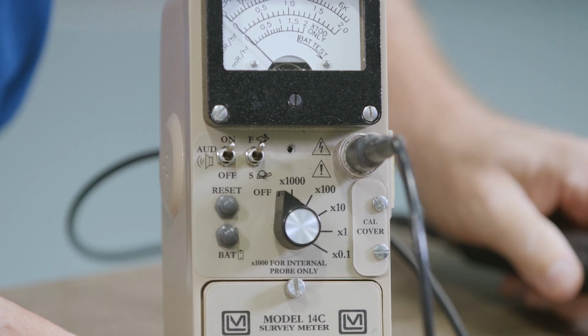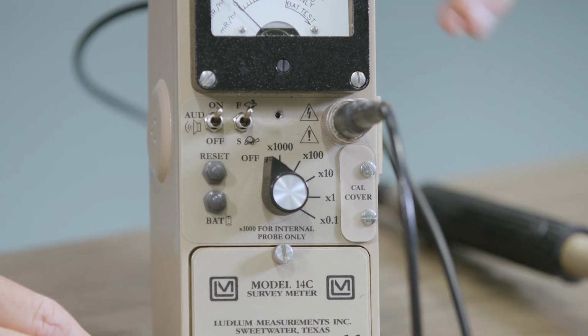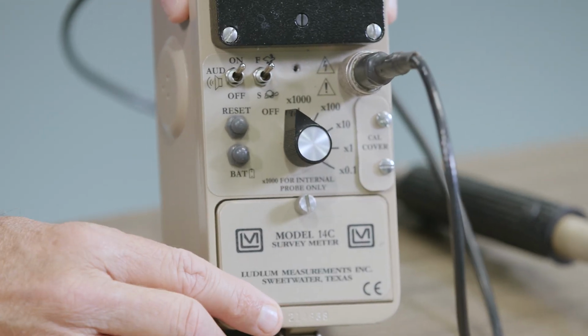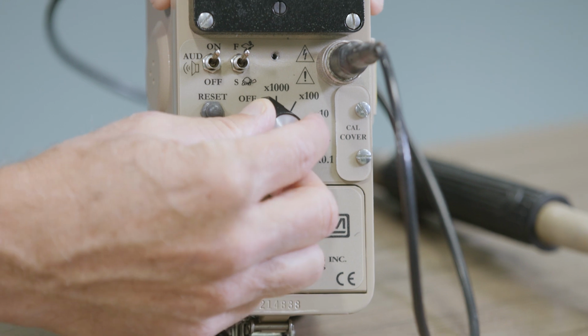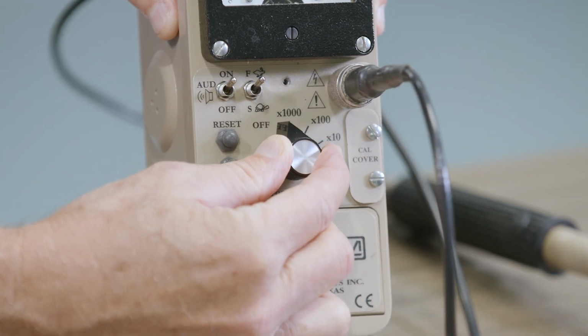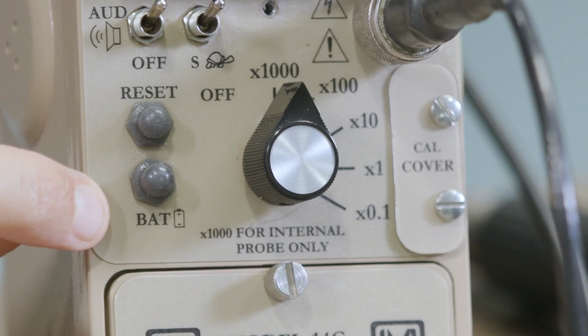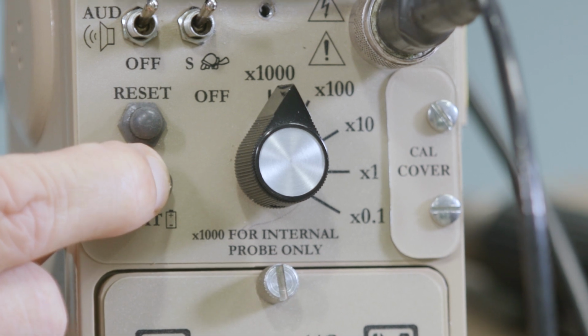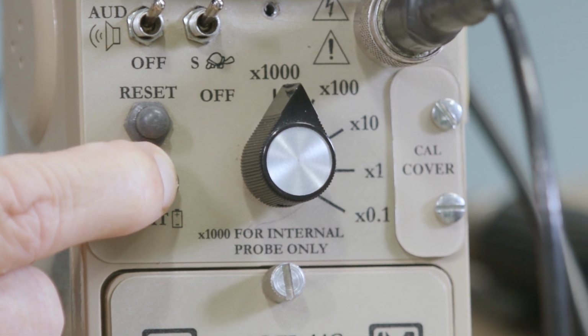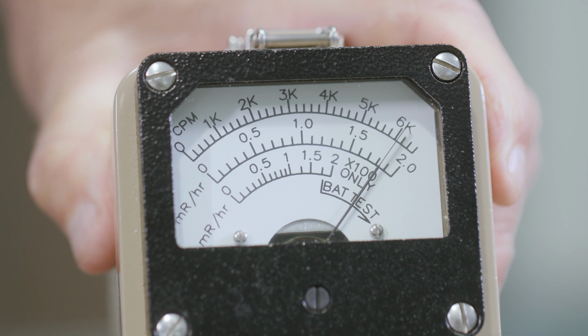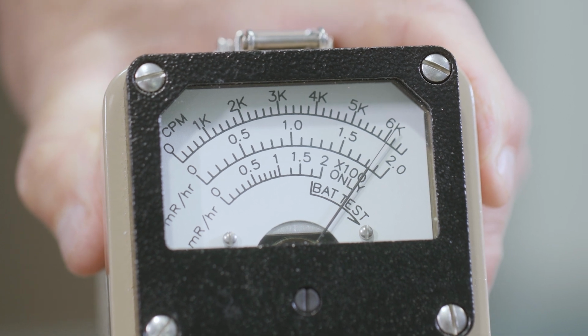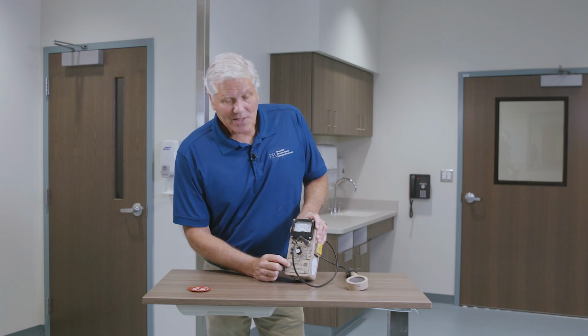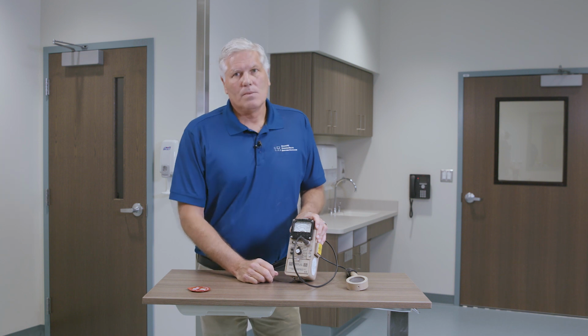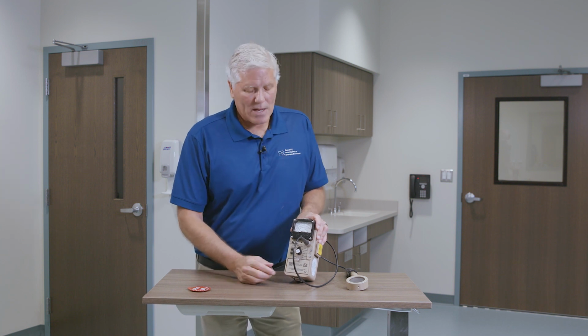Now we're going to do a quick battery test to make sure the battery is okay. It varies by meter, but simply in this case, we move the toggle off the off switch and we press the bat. And we can see if the needle deflects in the bat test, or sometimes called bat OK. If it is, the batteries are good.